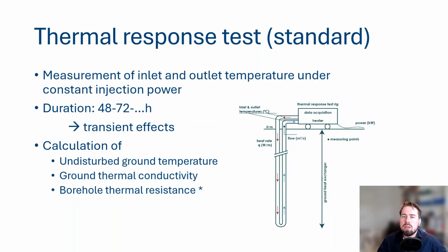It's first heating up the fluids, and afterwards it's heating up the grout, and then the heat goes to the ground. And we need this longer test in order for the thermal inertia of the fluid and the grout to be done.